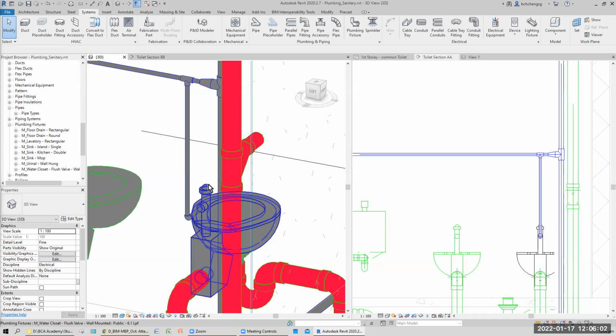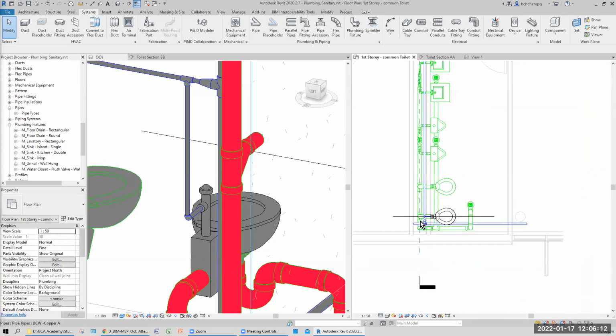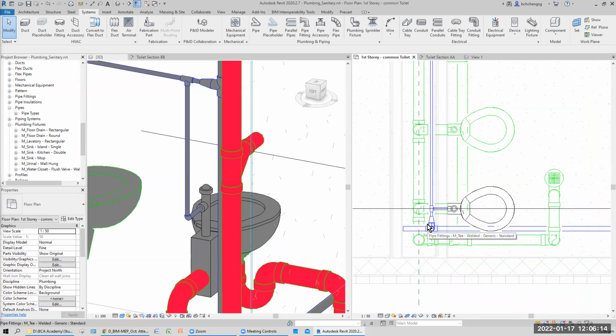So I'm not going to add any valve there because it's enclosed inside the building. I mean the cavity here, you see, in your plan here, there's a cavity. How am I going to add a valve and start to adjust? No way. Okay, so in certain details, if it's not required, then no need to do. Those that need to be visible, then yes. But of course, in drawing practice, all this must be highlighted to the main contractor.